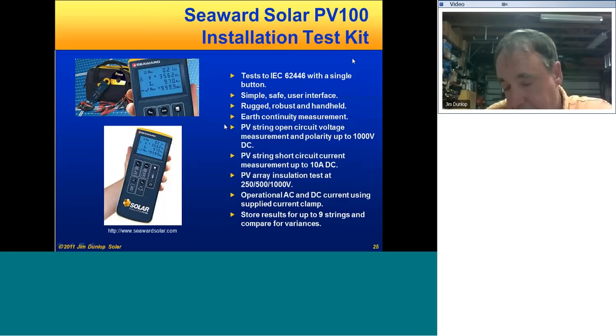You can also get Fluke insulation resistance testers. You can use voltmeters and clamp-on ammeters and other stuff to measure the other parameters, but this actually has all the equipment built in with the clamp-on DC-AC ammeter, the test probes. It actually short-circuits the array, puts high voltage across the array and the ground, and measures the resistance that way.